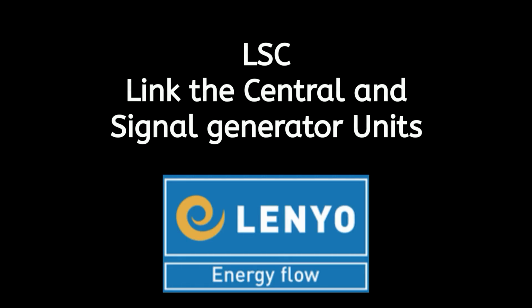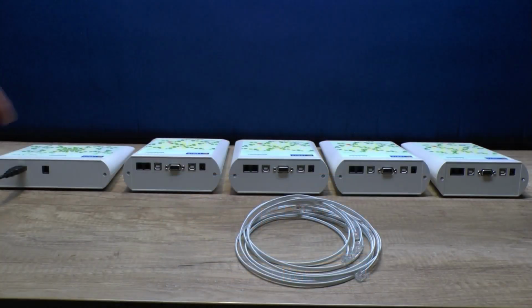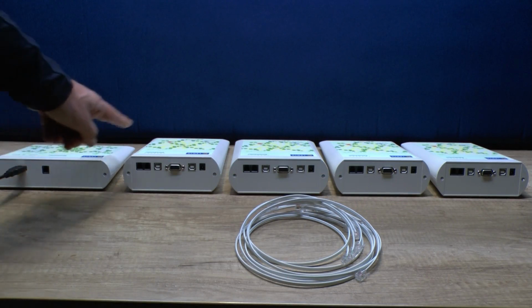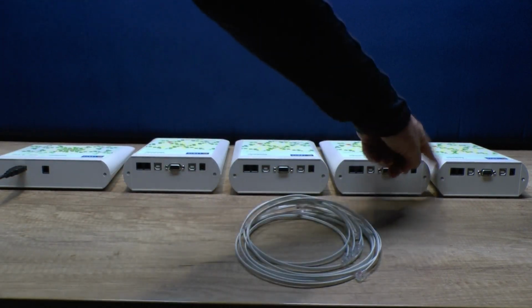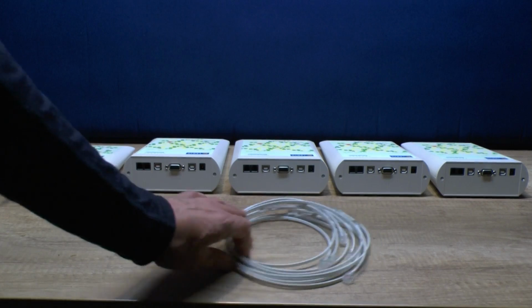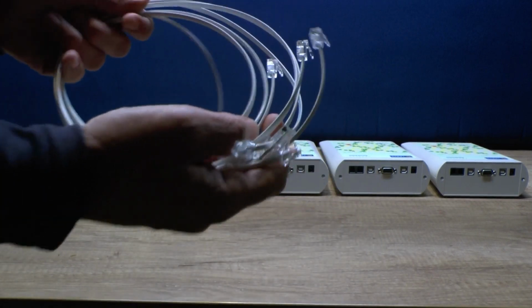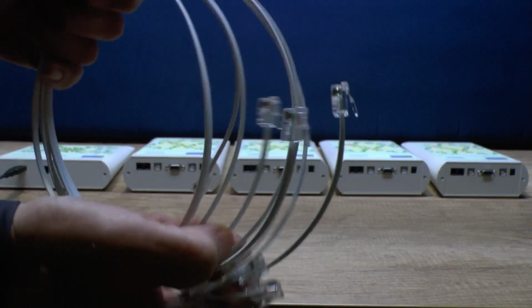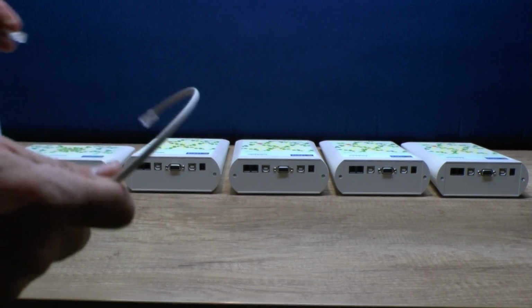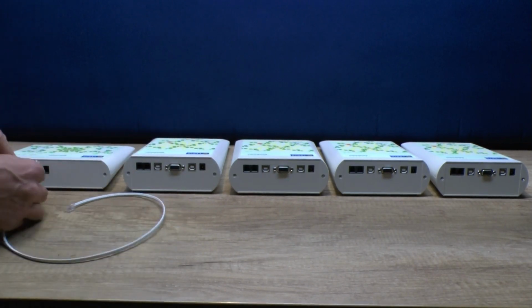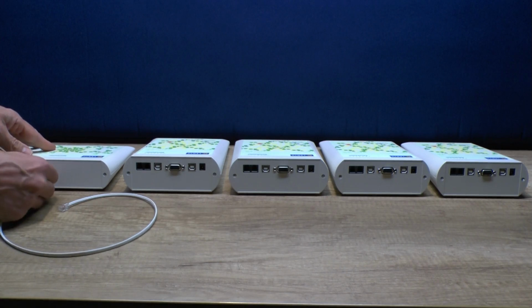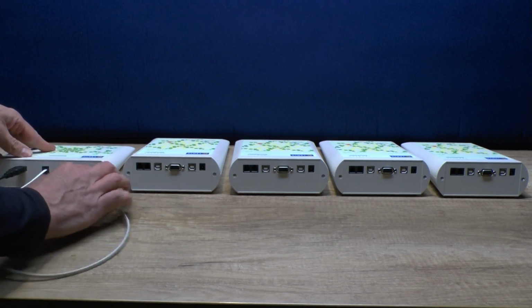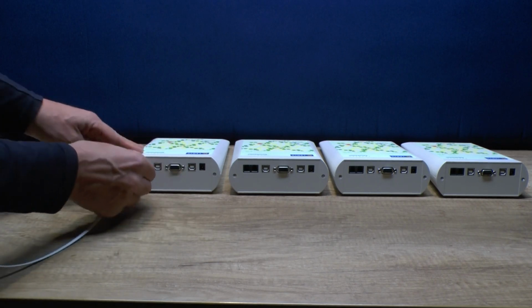Link the central and signal generator units. The next step is to link the central unit with the signal generators. For this, use the provided telephone cables. These are the cables we are going to use. First, fit one cable to the only phone socket in the central unit. And fit the other end of the cable into one of the phone sockets on the first signal generator unit.